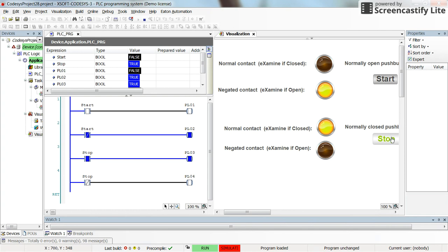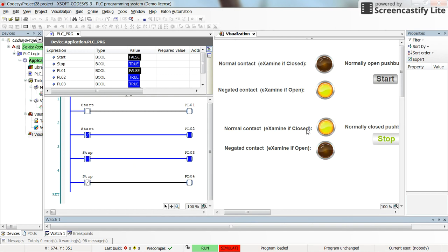Whenever I press the stop push button the logic is changed — the contact is opened, examine-if-open gives us a true value, and examine-if-closed gives us a false value, as you can see here in the ladder logic code and in the visualization.